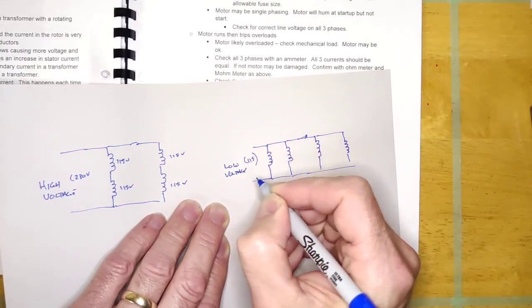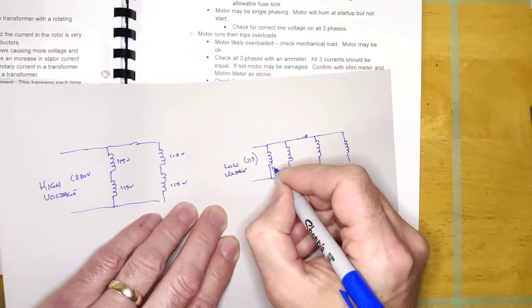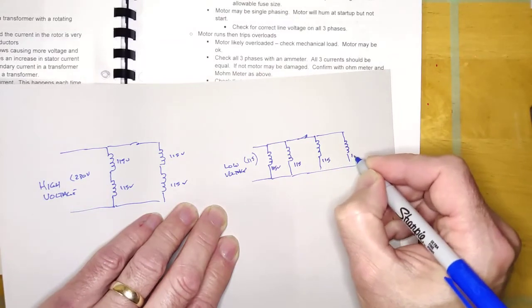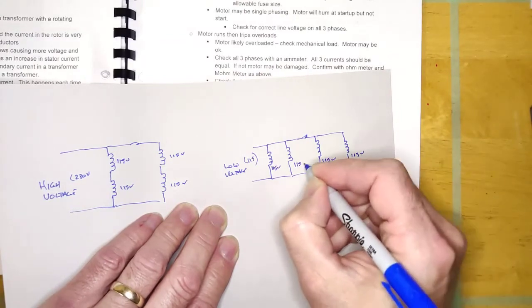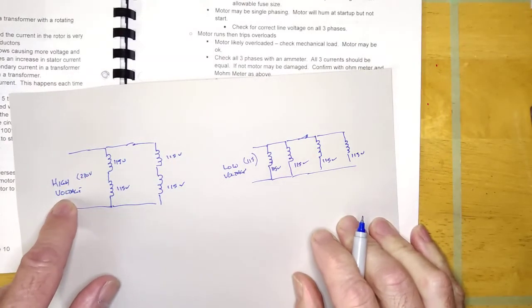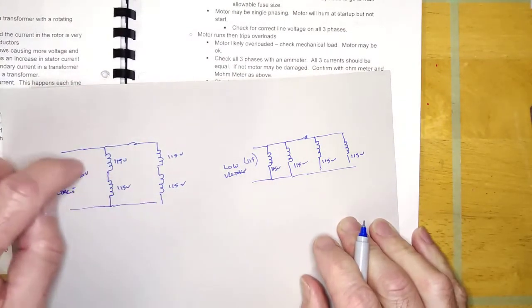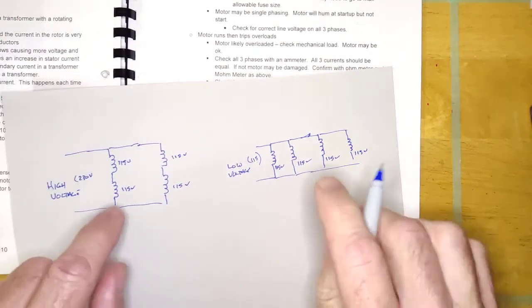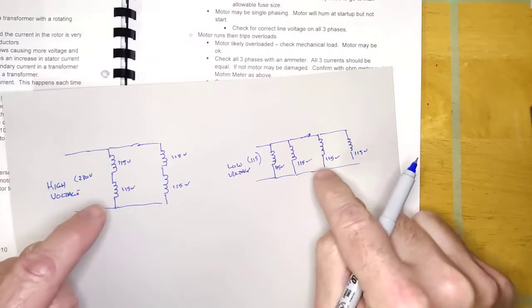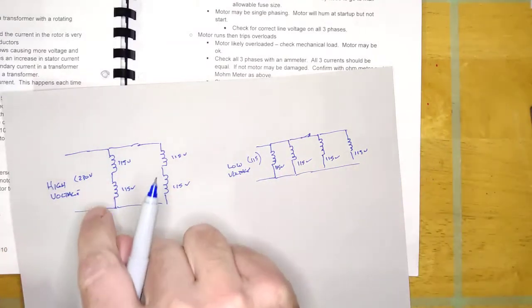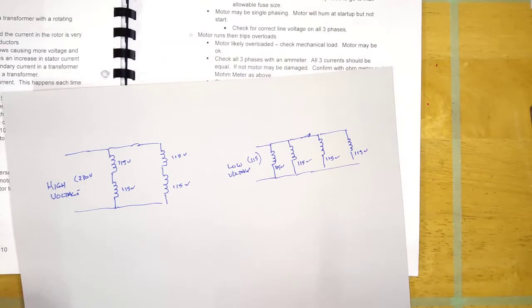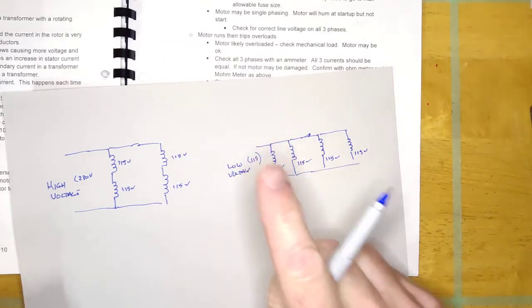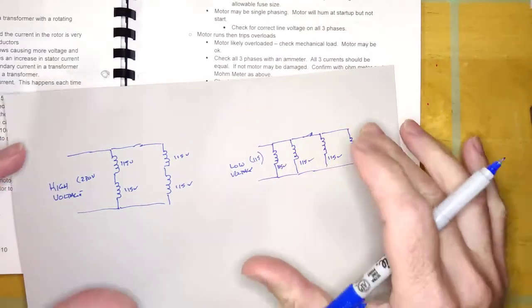And if you look at the configuration here, you'll notice that the 230 volts ties the windings together in series. And if you wanted to see that same motor wired low voltage, what you will see is the same two start windings, run windings, and the same two start windings. Here's the centrifugal switch. Here's the start.